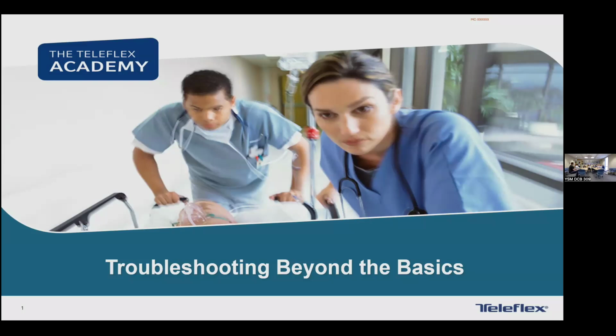I was asked to come and do some advanced troubleshooting so you understand how our pump monitors the helium and deals with it, and to give you some more tools when you have alarms. Our alarms are going to be similar but different, because we monitor helium differently than your previous pump. So we'll go through that and show you some actual examples from the troubleshooting that we had here.